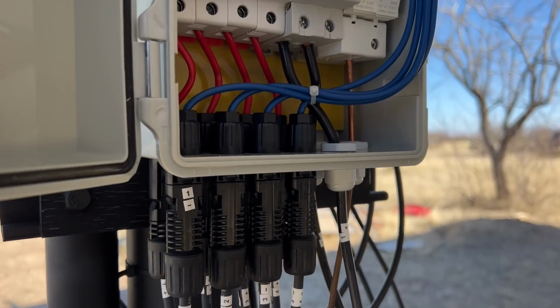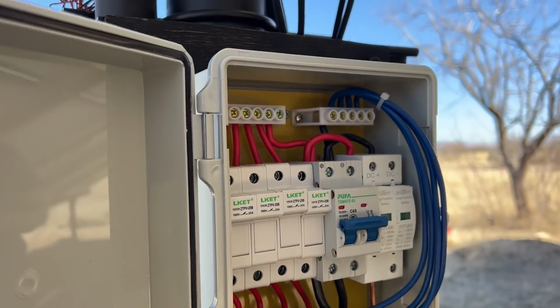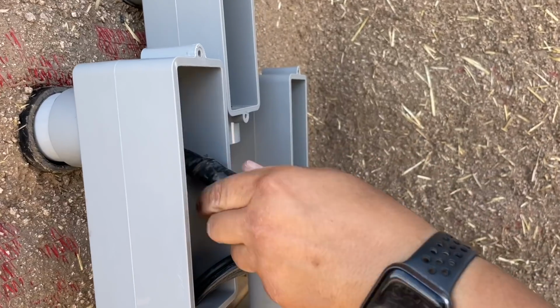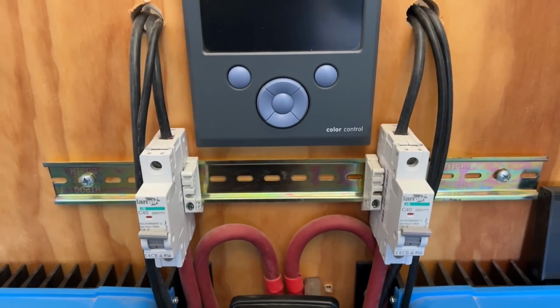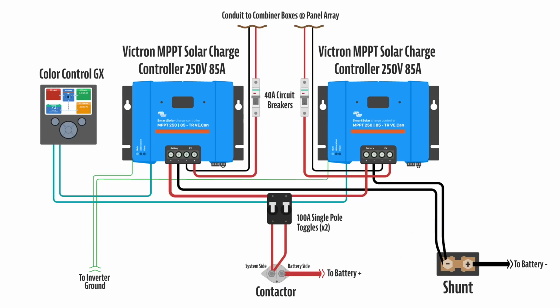As part of this, we needed quite a few additional cables and fuses, so let's talk through those. We had the PV wire coming in from the combiner boxes, which went through 40 amp, 250 volt circuit breakers, one for each set of power from each combiner box. Circuit breakers protect the system just in case the other circuit breakers at the combiner boxes were to ever fail, so there's extra protection. Out of that, we ran 2 gauge wires, so we needed black and red.